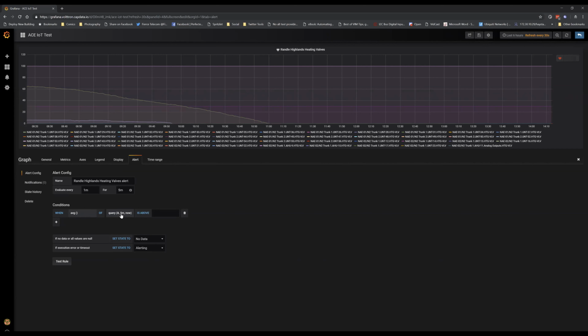And then you typically give it a time range, right? So I want the average over the last 5 minutes to be my trigger, so that a value has to be at a certain threshold for a certain amount of time. And so here we would say, pretty confident we're not going to generate a bunch of nuisance alerts by setting this to 120%.